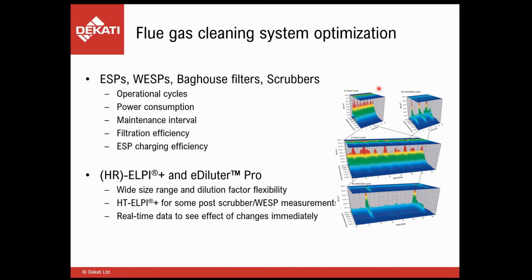Now with the dilution systems, we can measure directly before and after any of these cleaning devices to determine the filtration efficiency, of course, to determine what is the effect of the operational cycles of the cleaning devices, and try to optimize them to be as efficient as possible and to consume as little energy as possible.